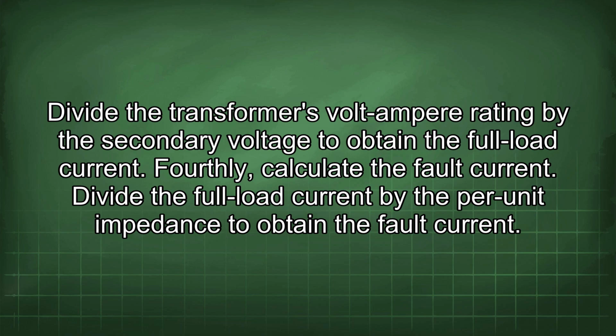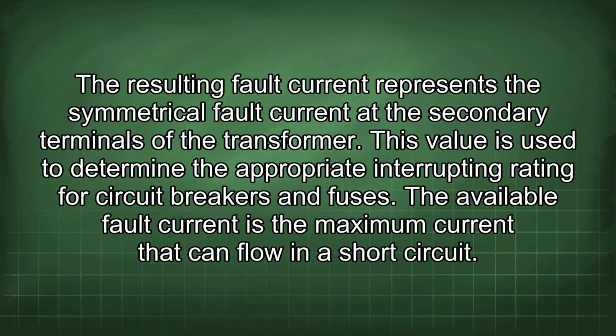Fourthly, calculate the fault current. Divide the full load current by the per unit impedance to obtain the fault current. The resulting fault current represents the symmetrical fault current at the secondary terminals of the transformer. This value is used to determine the appropriate interrupting rating for circuit breakers and fuses.